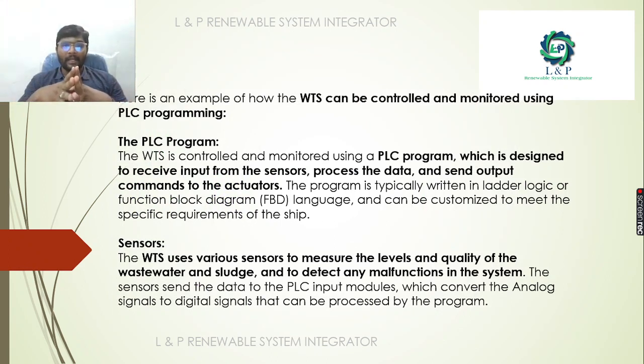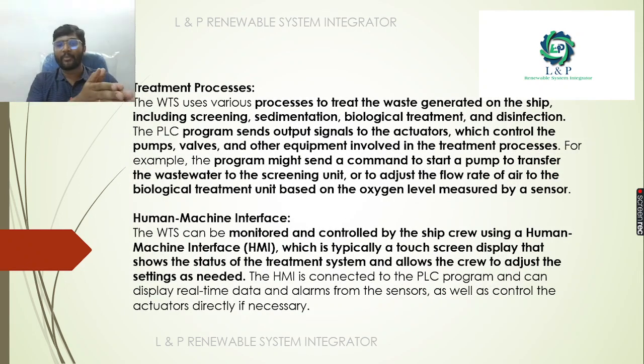Next, how this wastewater treatment system works, how it is monitored and controlled. First thing is that using different sensors, we will take the inputs, and using the actuators, we will make the commands. Most importantly, we are using the sensors to measure the level and quality of wastewater and sludges, and to detect any malfunctions in the system. If we are going for a treatment process, it processes the waste generated on the ships, including screening, sedimentation, biological treatment and disinfection. So output signals will be sent to the actuators, which control the pump, valve and other equipment involved in the treatment process. Say for example, it sends a command to start a pump to transfer the wastewater to the screening unit, or it adjusts the flow rate of the air to the biological treatment unit based on the oxygen level, which is being measured by the sensors.